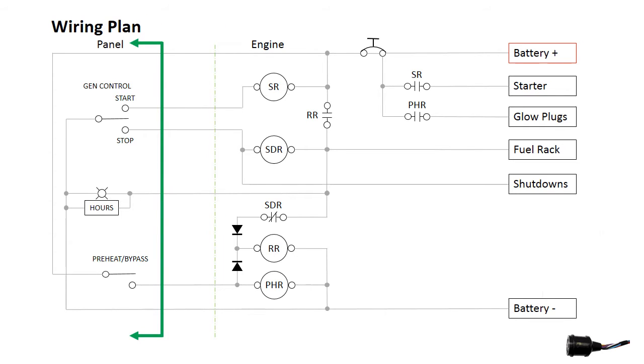The next section is the control panel, which contains control switches and panel meters. The preheat and shutdown bypass switch activates the preheat relay for cold engine starts, and also keeps the engine running until oil pressure builds up right after starting. The generator control switch provides start and stop control.